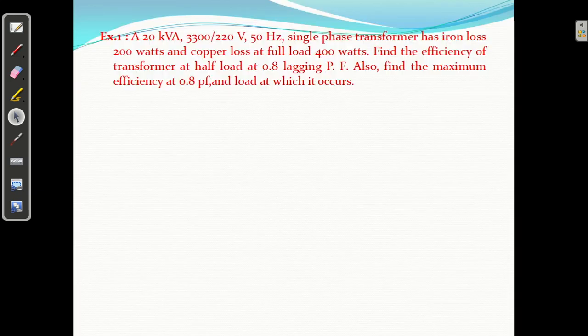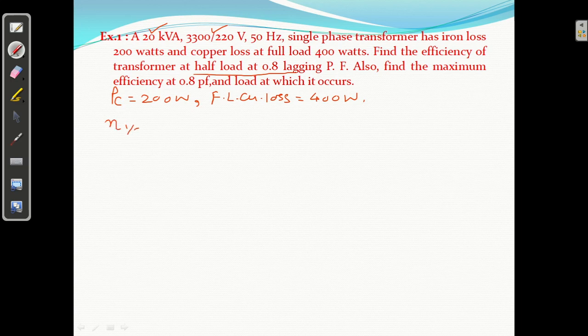Okay. So this is the first problem we have: a 20 kVA, that is the rating we have given. The primary voltage is 3300 volt and secondary is 220 volt, right? A 50 Hz single phase transformer has iron loss Pc given as 200 watt, and we know iron loss will always be constant at all loads, right? And full load copper loss is given as 400 watt, right? Find the efficiency of the transformer at half load at 0.8 power factor.